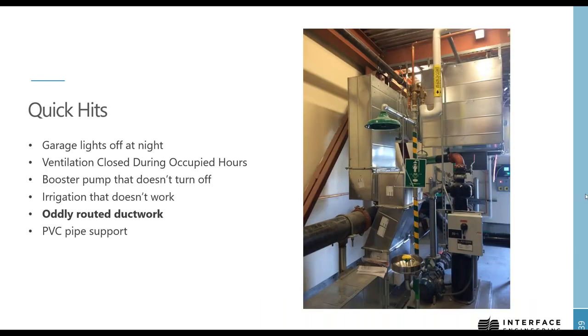And then the final example that I've got is sometimes what is on paper has to work around things, and actual conditions out on site can change the routing of ductwork quite a bit. In this case, we see what was probably drawn up as a very straight duct, resulting in all these extra elbows, all these little turns and curves and switchbacks. And what actually happened in this situation was this was meant to be an exhaust system for a refrigerant monitoring system in a chiller room.